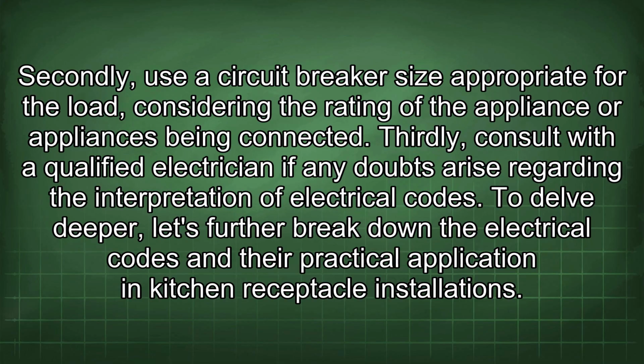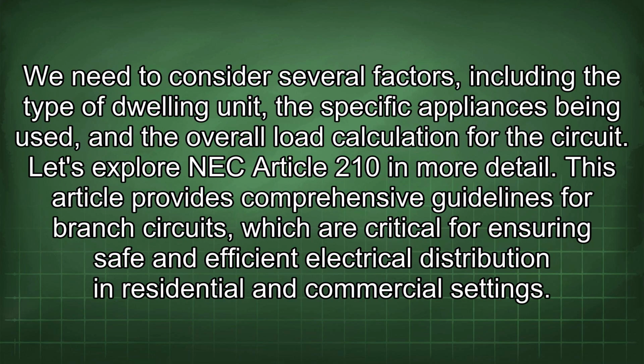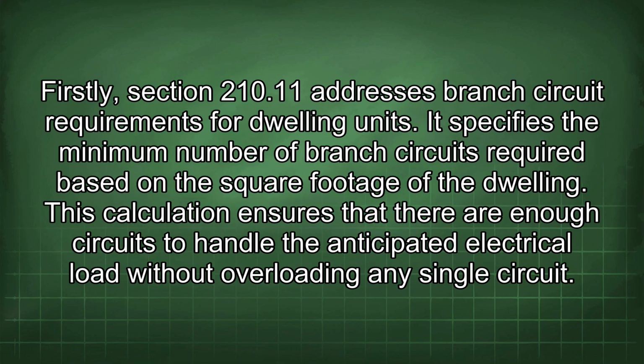To delve deeper, let's further break down the electrical codes and their practical application in kitchen receptacle installations. We need to consider several factors, including the type of dwelling unit, the specific appliances being used, and the overall load calculation for the circuit. Let's explore NEC Article 210 in more detail. This article provides comprehensive guidelines for branch circuits, which are critical for ensuring safe and efficient electrical distribution in residential and commercial settings. Firstly, Section 210.11 addresses branch circuit requirements for dwelling units.